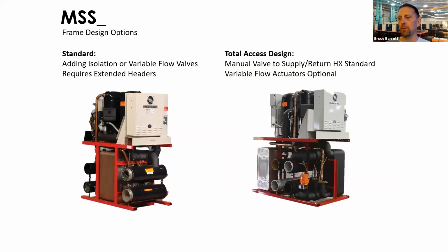Within that family, we've improved our product over the years to make it more accessible, more maintainable in the field. So the left is our old design, the right, our total access design, has the header pipes down the middle, has the heat exchangers on the outside. You can easily sit on a bucket here, isolate electrically this module, power it off for safety. I can pull a variable flow valve off. I can pull a heat exchanger off by isolating that water circuit. I can back flush heat exchangers one at a time. I don't need to do them all at once. I don't need to take my chiller plant down, but that makes it completely serviceable from the outside of the unit. This is probably 95% of what we sell now is the total access design, just because of the ease of maintenance.